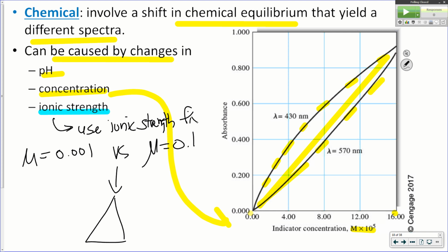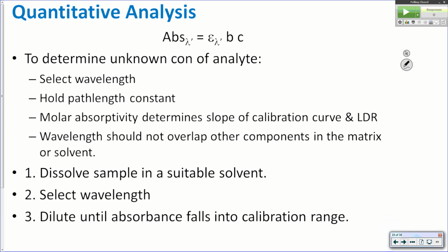And what this simply is, is a solution of very high ionic strength that is added, like in a 1-to-10 ratio, to all the samples and the buffers. It would overpower any ionic strength that's coming from the sample and let it be at a fixed ionic strength, comparing samples to standards. So ionic strength fixers are used if that becomes the case. And all you need to do is create a salt with it. It's going to have a very high ionic strength in the system.